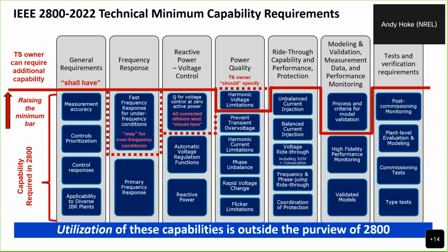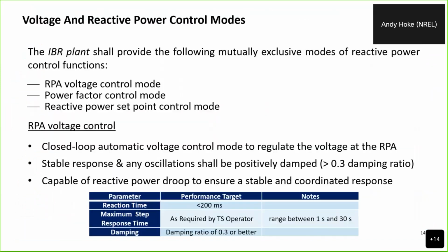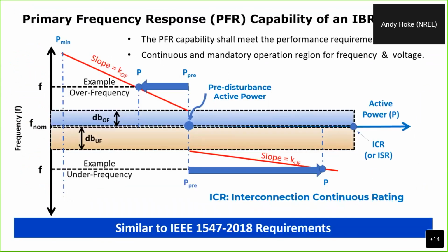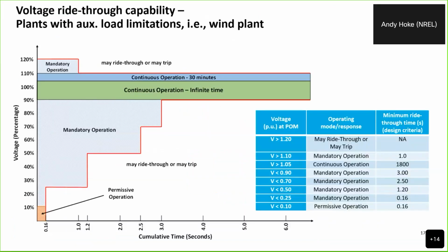This slide just talks about some of the details that are in IEEE 2800. What are we going to find in there? I'll let folks read that offline because there's a lot in there, but you can basically see that it includes things from reactive power control, power quality, ride through, frequency response, etc. It includes details on voltage and reactive power control modes. I'm going to go through that quickly. It includes details of primary frequency response and fast frequency response requirements. It includes details of ride-through requirements.